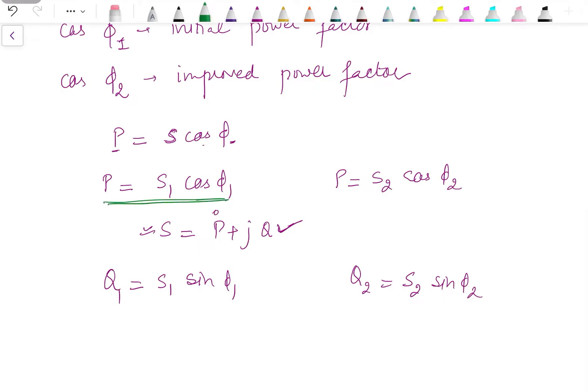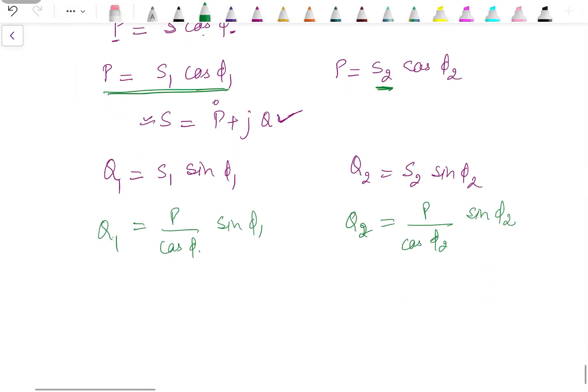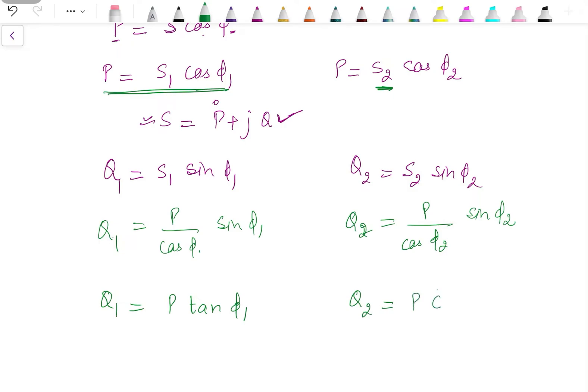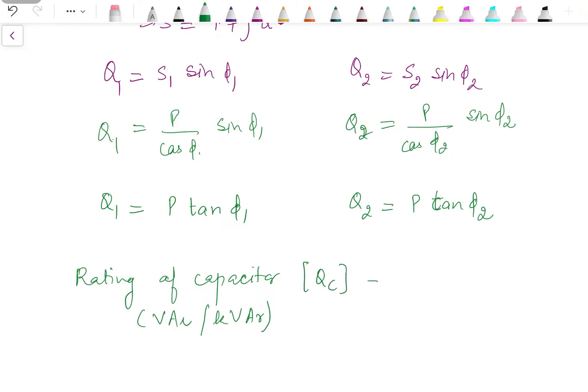Substituting S_1 = P/cos φ_1 and S_2 = P/cos φ_2, the reactive power at initial power factor cos φ_1 is P tan φ_1, and it changes to P tan φ_2 when we add the capacitor. So the rating of the capacitor, in VAR or kVAR, denoted by Q_C, represents the change in reactive power.